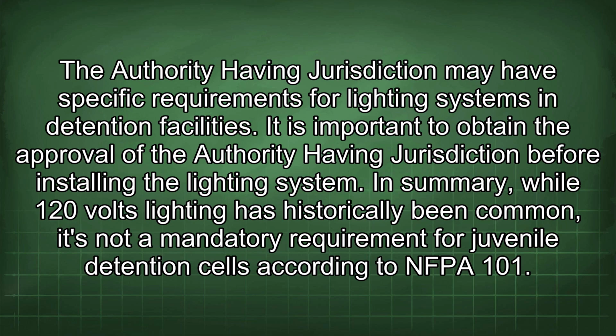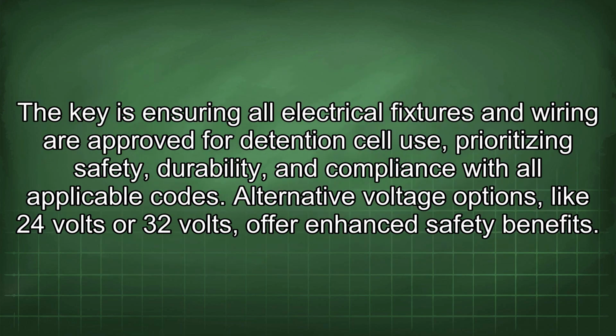In summary, while 120 volts lighting has historically been common, it's not a mandatory requirement for juvenile detention cells according to NFPA 101. The key is ensuring all electrical fixtures and wiring are approved for detention cell use, prioritizing safety, durability, and compliance with all applicable codes. Alternative voltage options like 24 volts or 32 volts offer enhanced safety benefits.